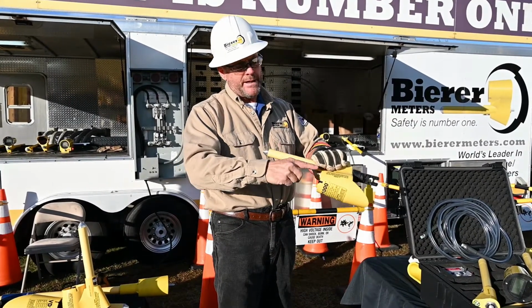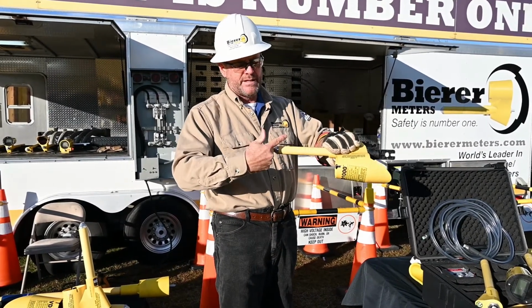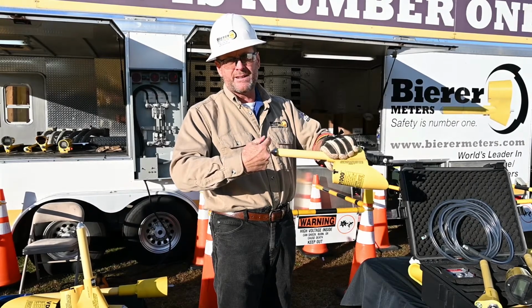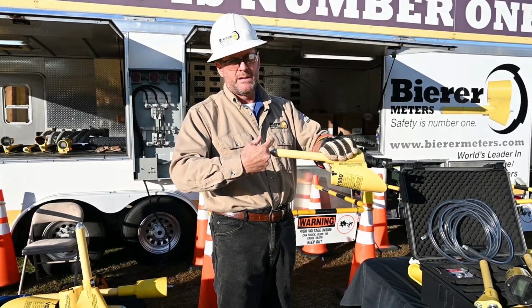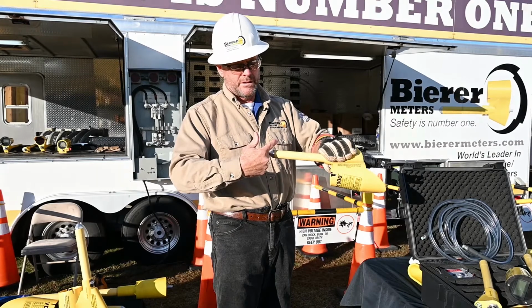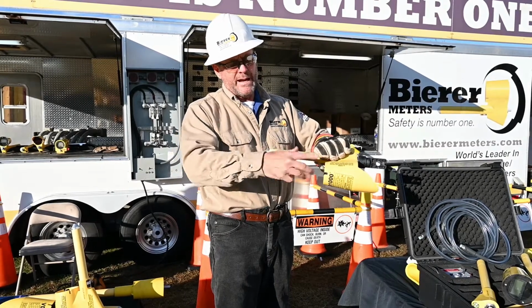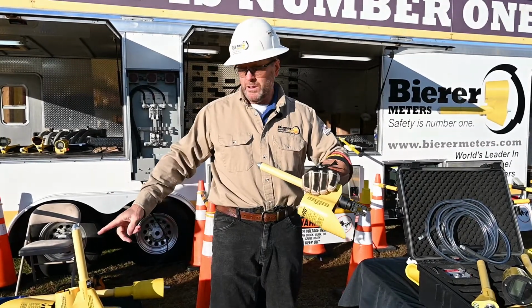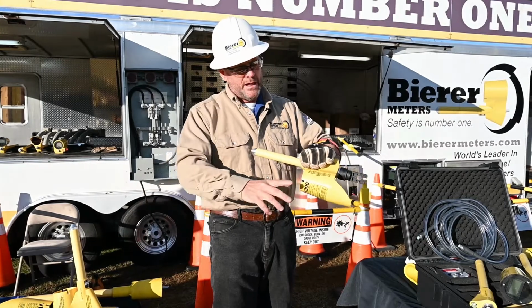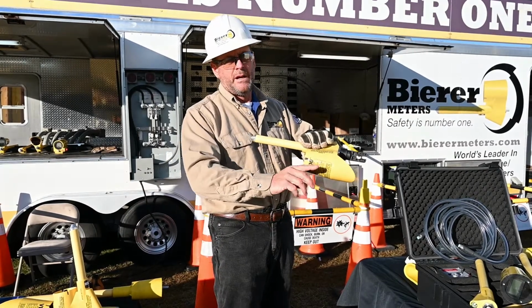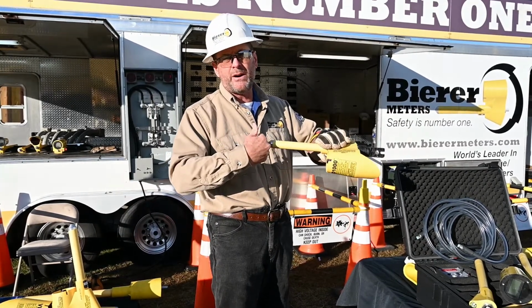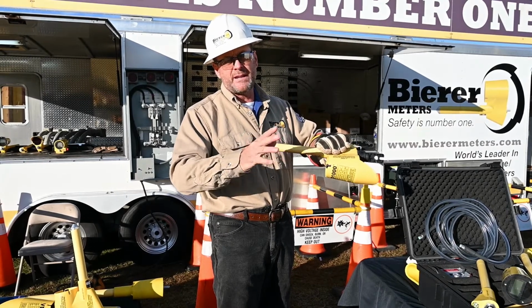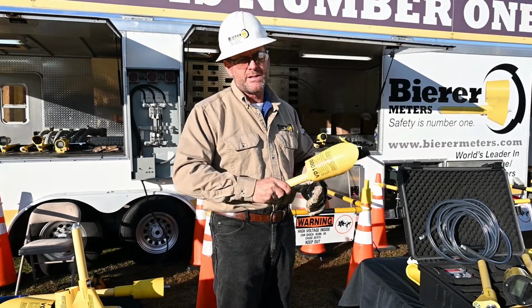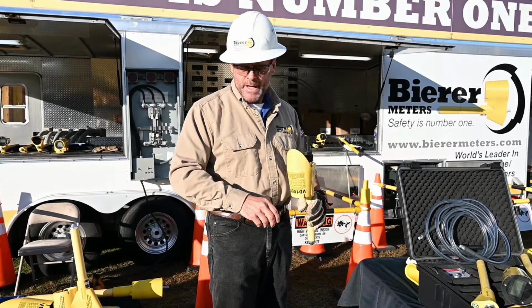That way the meter head is not being influenced by the capacitance on these other conductors, the corona, that field. If you've got a ground plane, maybe a corner pole, say from Mississippi, with a ground on it, you don't want that meter head close to that ground. It's going to give you a funky, skewed reading. So it's important.